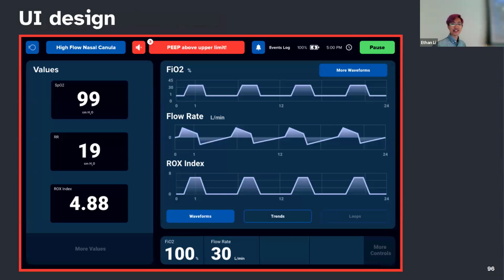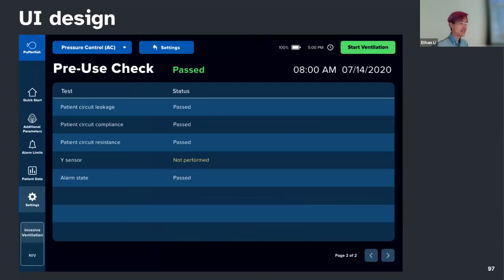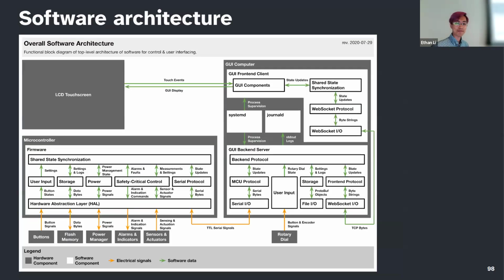Finally, safe operation of the ventilator required a user interface which would help really busy and multitasking clinicians to understand patient conditions and then make appropriate decisions quickly. And the clinicians would also need to have enough information to take corrective actions appropriately in case of a technical problem with the device, for example, a software failure. Other features also had to be implemented, including various safety check procedures and things like battery lifespan monitoring. Because of all these decisions in hardware and UI design to rely heavily on software for implementing various safety mechanisms and safety checks, a lot of complexity was pushed into the software.